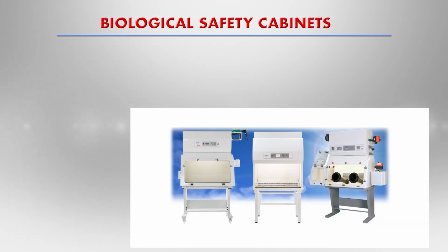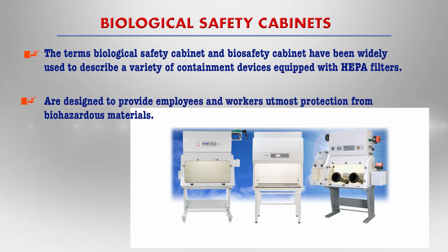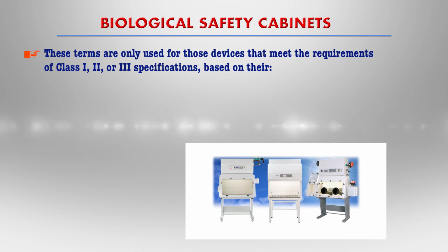Let us now first discuss the biological safety cabinets. The terms biological safety cabinet and biosafety cabinet have been widely used to describe a variety of containment devices equipped with HEPA filters. We will also see what this HEPA filter means. They are designed to provide the employees and workers utmost protection from biohazardous materials. These terms are only used for those devices that meet the requirements of the class 1, 2 or 3 specification. We have already discussed these class specifications.